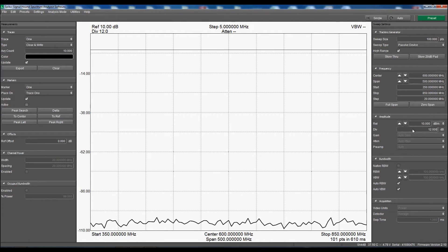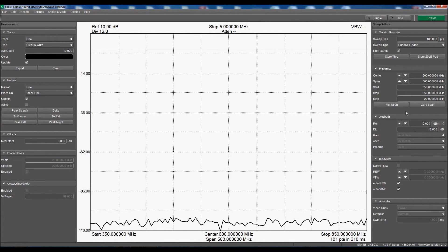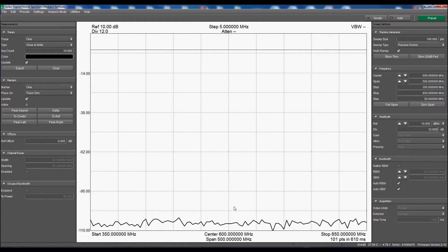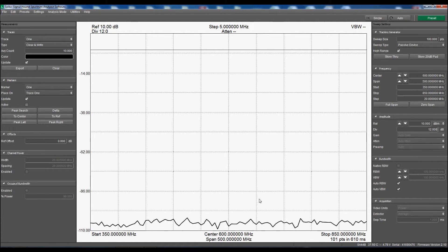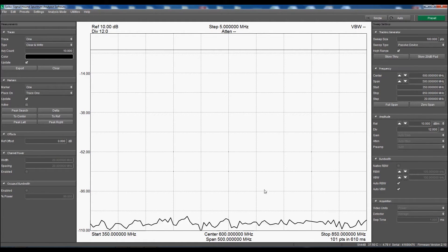Let's take a look at the noise floor for this measurement by measuring an open — I'll just disconnect it here. It's off screen, so let's change our scale to 12 dB per division. It looks like it's somewhere around 100 dB, so measurements down to 90 dB or so should be OK.